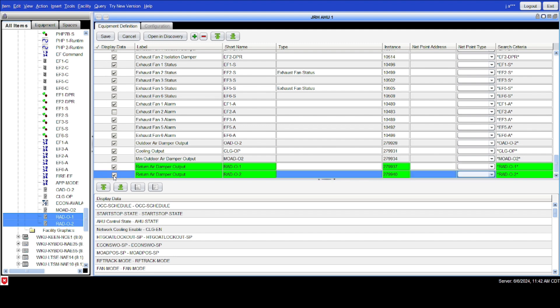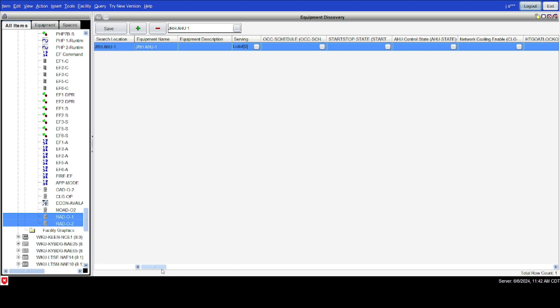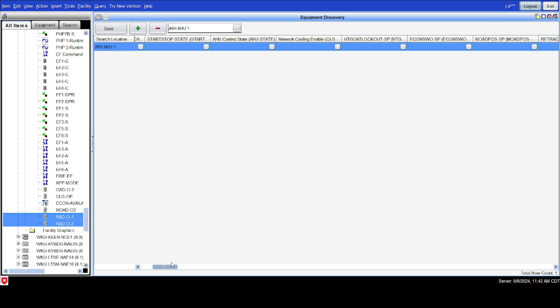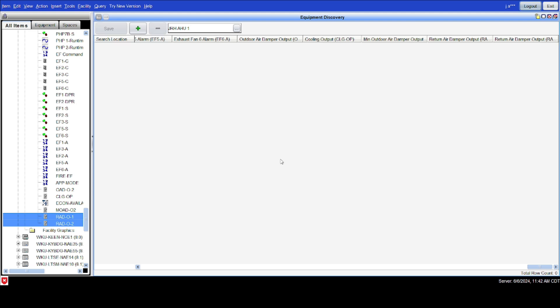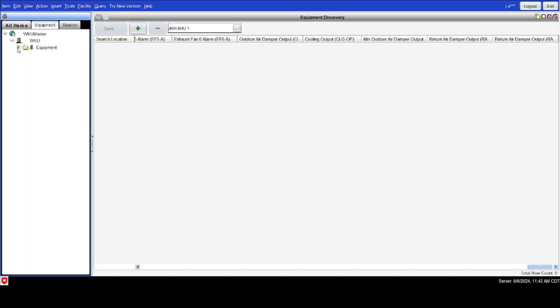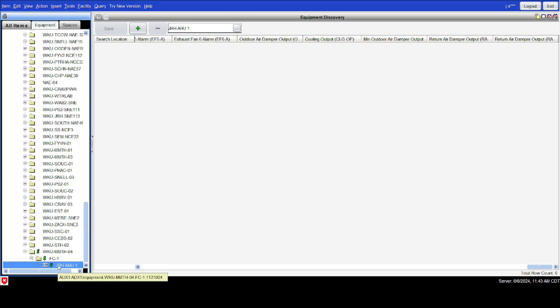When I drop them there and scroll down you can see the two new points. I'm going to select those so they will appear on my display. Once I select them, I hit the save button and then open in discovery. This is basically all of those previous points. We're going to save this, but then come back and delete the equipment object that it creates — because anytime you do something like this it will create a separate equipment object, and we don't necessarily want that.